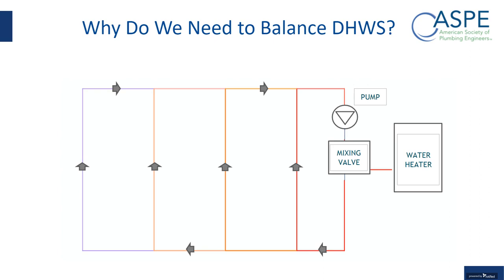So we have our water heater, our mixing valve, and our pump, and then 4 risers going from right to left. As we all know, water goes to the path of least resistance. In this sketch with no balancing, the first riser immediately to the left of the mixing valve has the path of least resistance, and it also has the least amount of heat loss because the piping is a lot less than it is in the other ones.